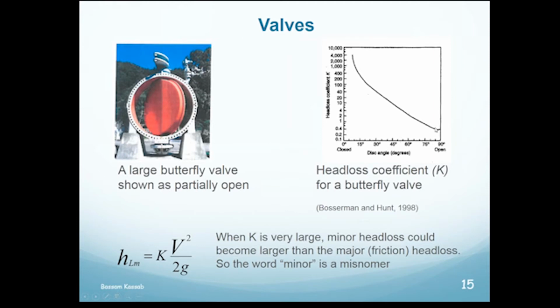That's an example of how the K value could change from 0.4 when it's totally open to around 10 when the valve is 45 degrees open, which means 50% open. When the degree of opening is just 10 degrees, the K value could be 1,000, even going up to 4,000 or higher. When you totally close the valve, the K value is infinity, but the velocity is 0. So it's important to know that the K value becomes larger and larger as you close the valve.